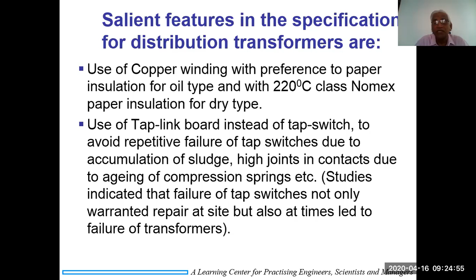Salient features and the specifications of distribution transformers are use of a copper winding with preference to paper insulation for the oil type, with 220 degrees centigrade class Nomex paper insulation for dry type, use of a tap link board instead of a tap switch to avoid repetitive failure of tap switches due to accumulation of sludge, high resistance joints in contacts due to aging of compression spring, etc. Studies indicated that the failure of the tap switches not only warranted repair at site but also at times led to the failure of the transformers.